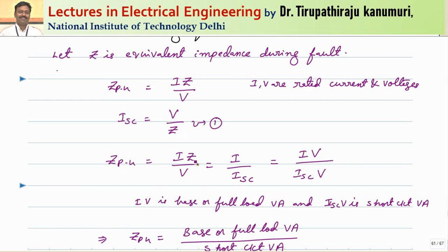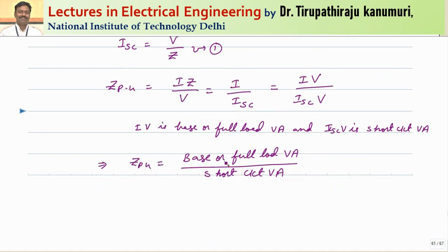Z per unit equals I·Z divided by V, and since V divided by Z equals ISC, Z per unit is therefore I divided by ISC. Multiplying numerator and denominator by V gives I·V divided by ISC·V. The rated current multiplied by rated voltage equals the rated volt-ampere, or full load volt-ampere of the system — generally represented in MVA.